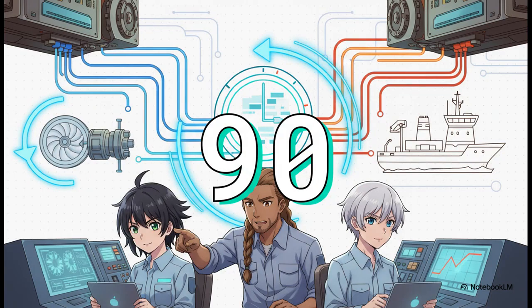Keep this number in your head: 90 seconds. A generator can be started up to 90 seconds after pre-lubrication stops. That is a vital metric in our checklist for evaluating system reaction times during an emergency generator shutdown. It's essentially your guarantee of a rapid blackout recovery, which is exactly why we strictly govern the test procedures for the automatic starts of standby generators.